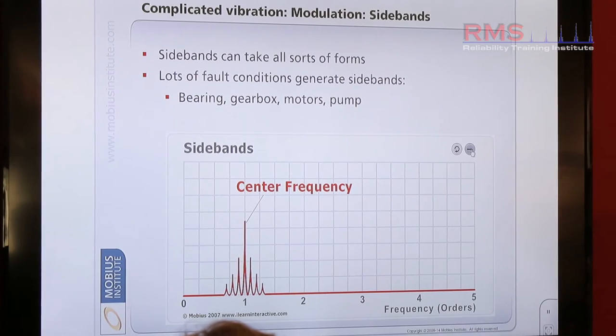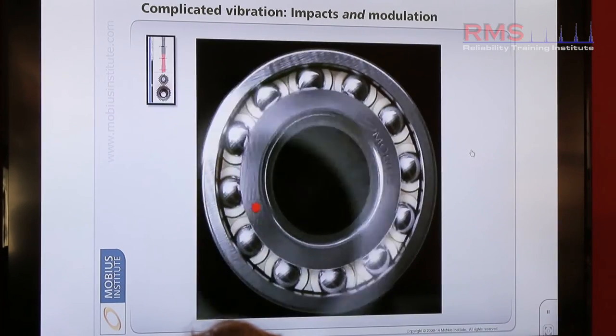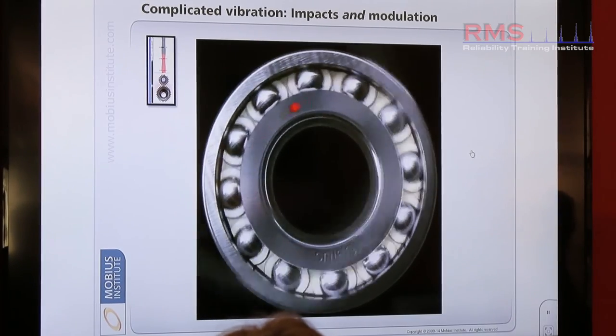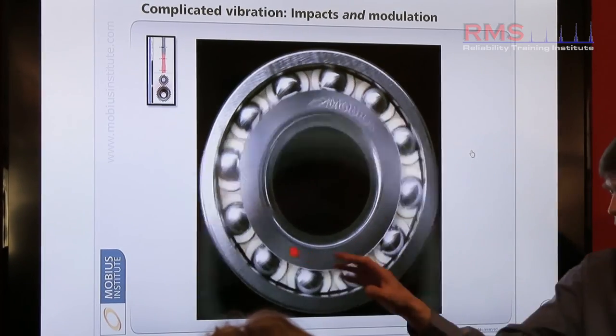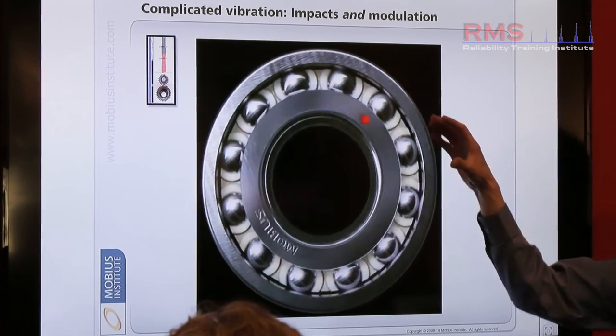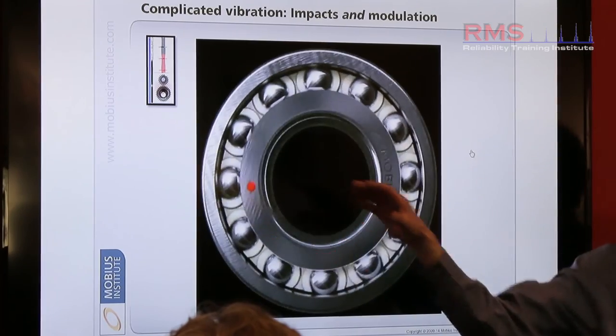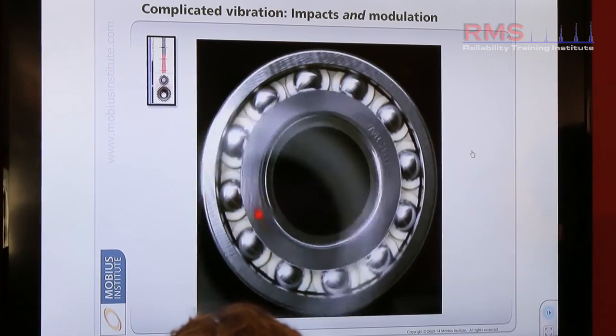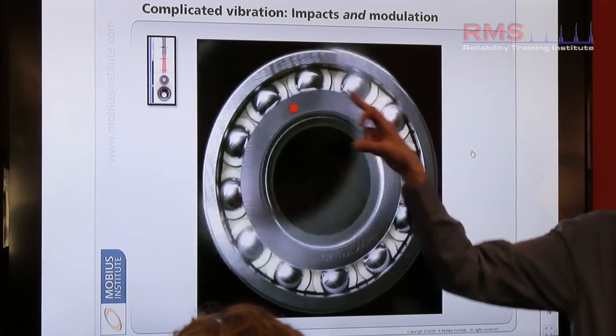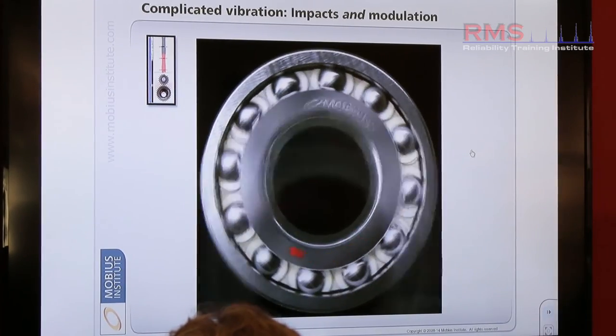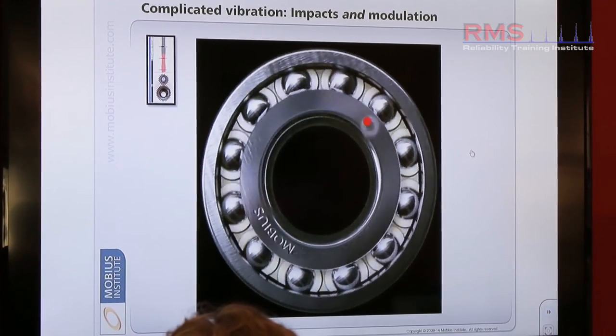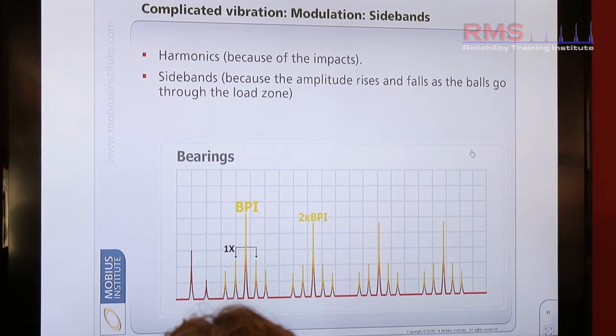And again, there are some more sidebands. Maybe if the defect — that red dot is inside the bearing, there's a pitted damage spot. When the defect enters the lower part of the bearing due to gravity, the forces are greater, so we get a stronger signal. Then as the defect travels out of the load zone towards the top, the signal weakens, and it goes stronger again. And that will cause a distinct pattern — sidebands.